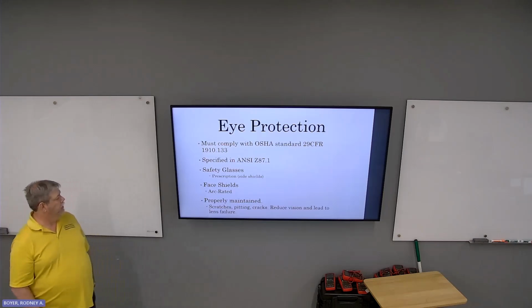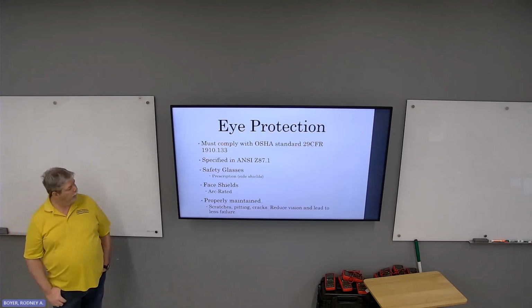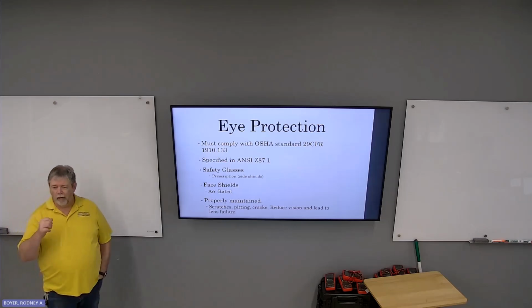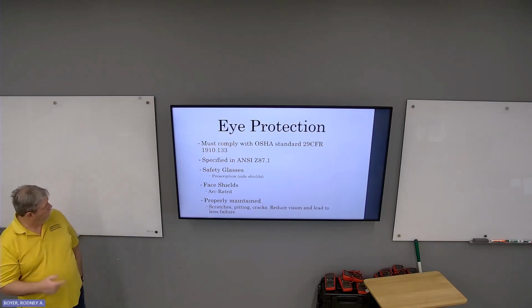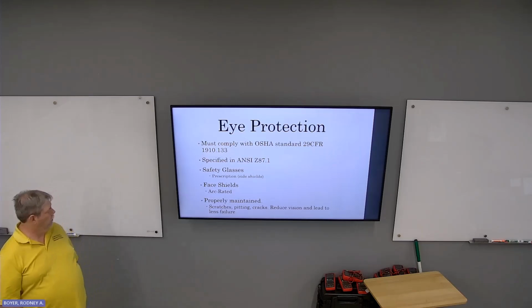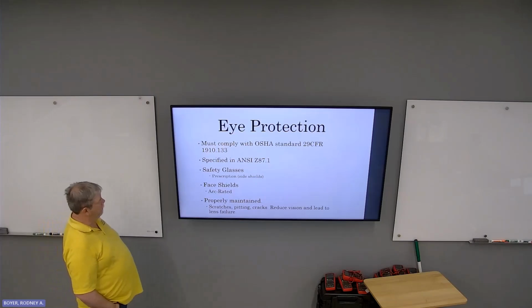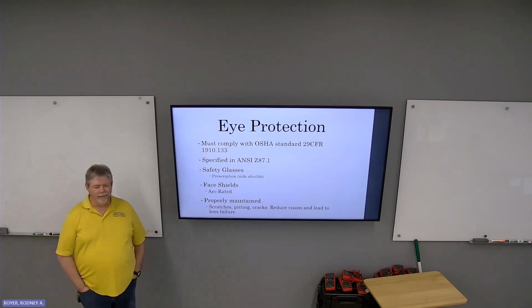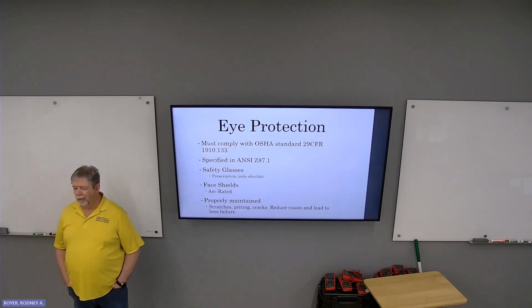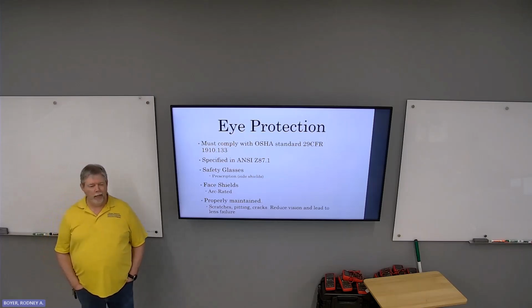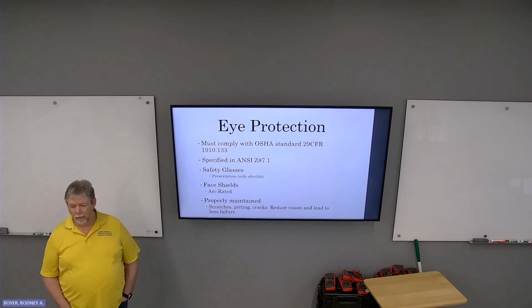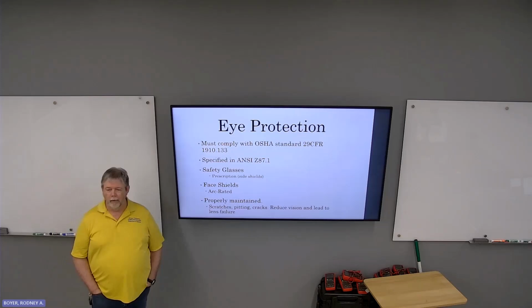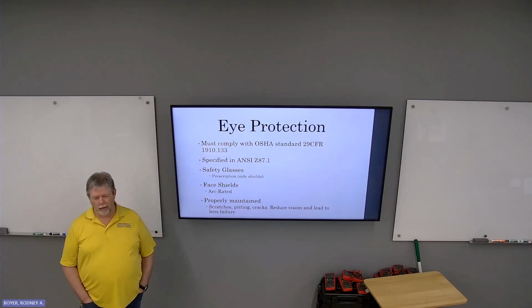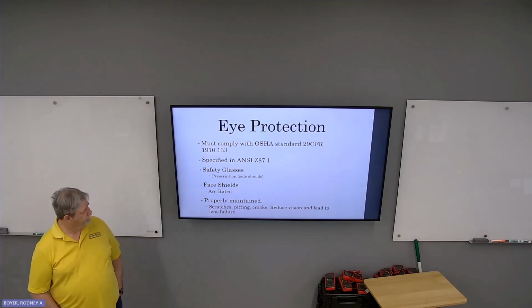Face shields are typically arc rated, but don't have to be. Most of them are polycarbonate because it is impact resistant. Has to be properly maintained, which means you have to check them regularly for scratches, pitting, cracks. That reduces your vision and may lead to lens failure. Last thing you want to do is have something come flying at your safety glasses that are already compromised and either go through them or cause them to shatter and that go in your eye. That would not, either one of those, be a good time.